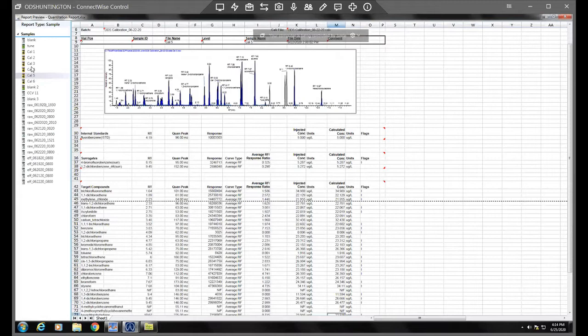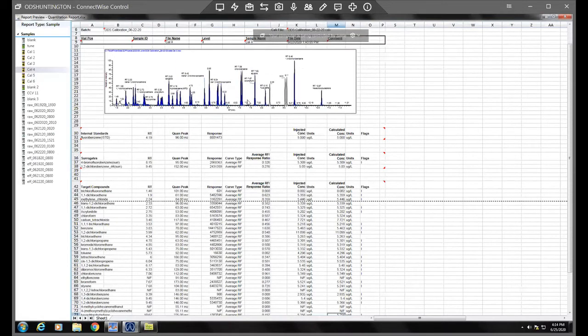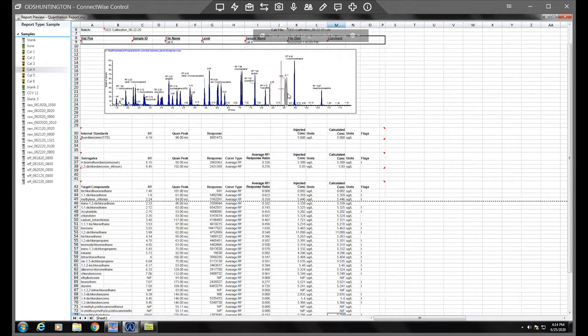So we're on the cal4 file here. So you can see that like these three peaks were not integrated. So before I would go and adjust them, I would verify which peaks they are.